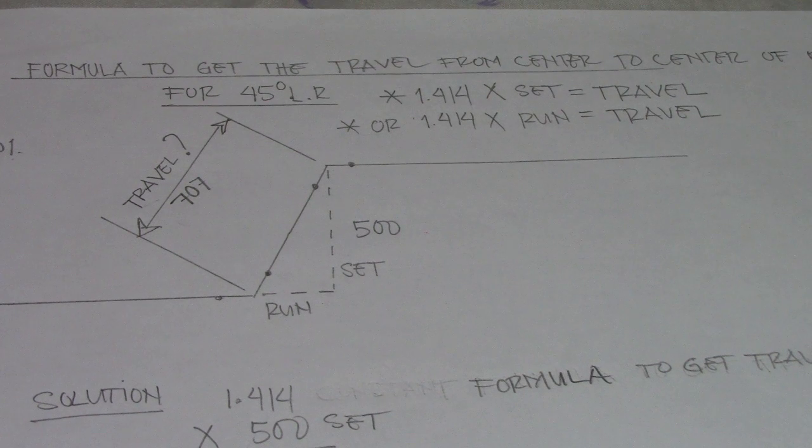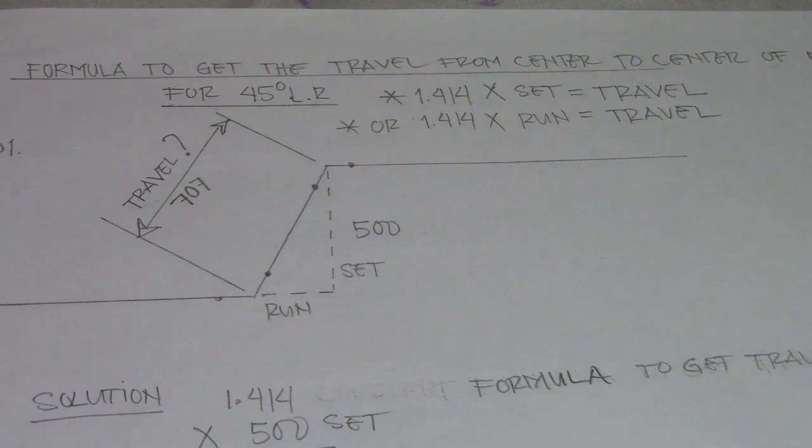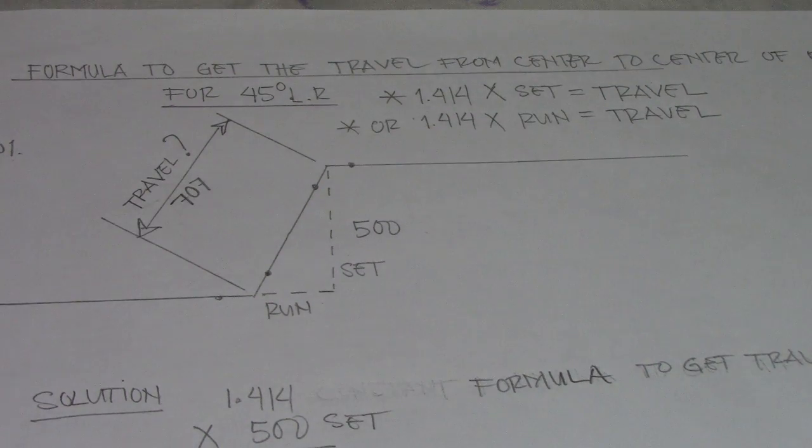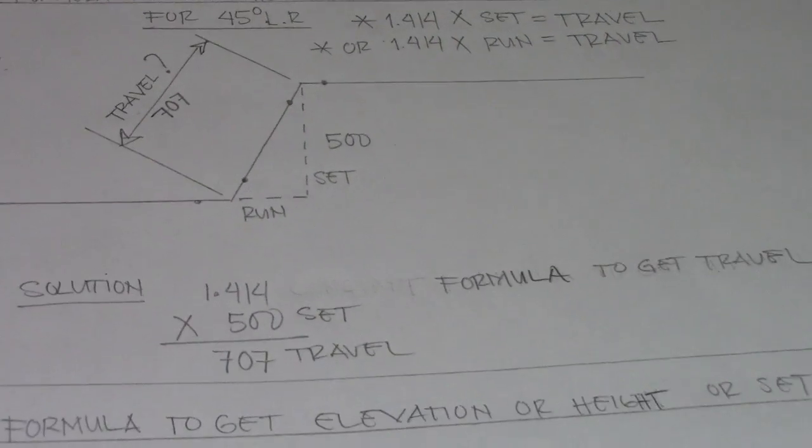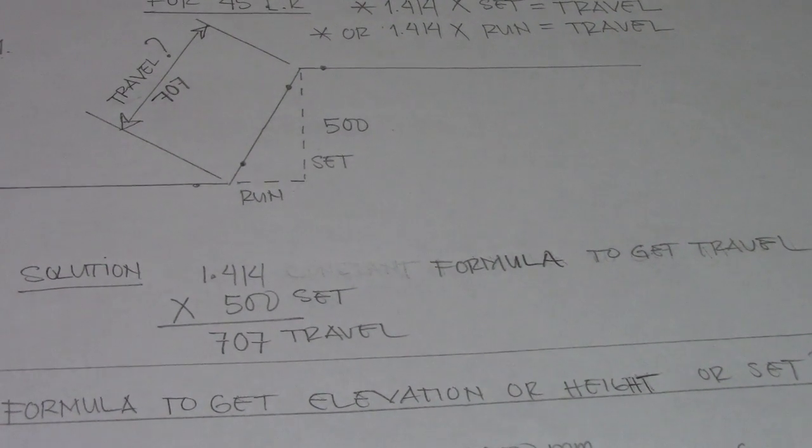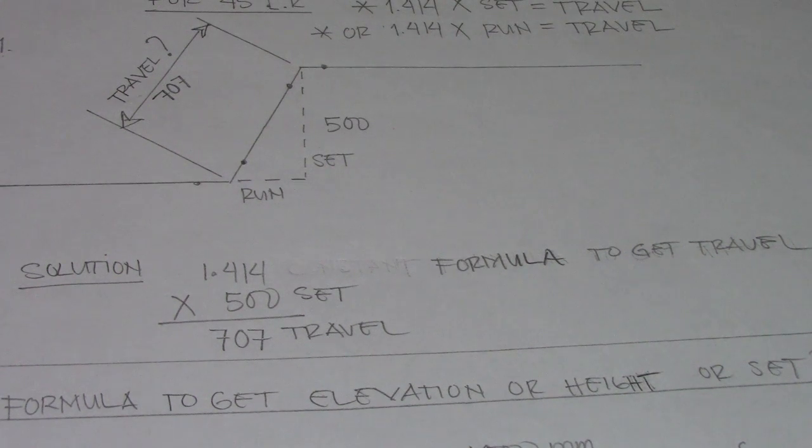So the answer: 1.414 multiply by set equals travel, which is 707. This is the answer. This is a very easy way to find the travel. Here is our solution: 1.414 multiply by 500 equals travel. This formula is only for 45 degrees, long radius.